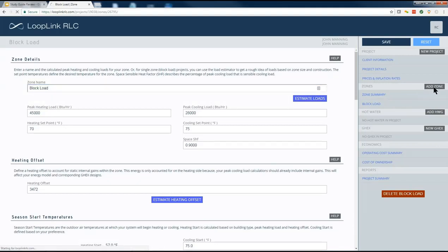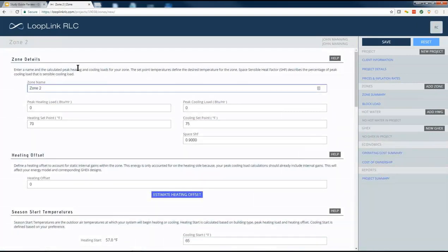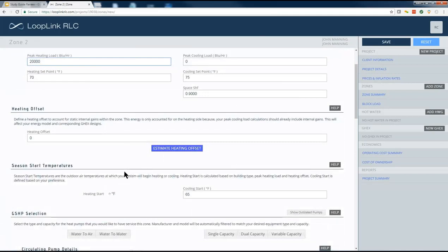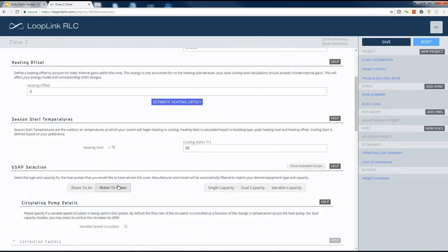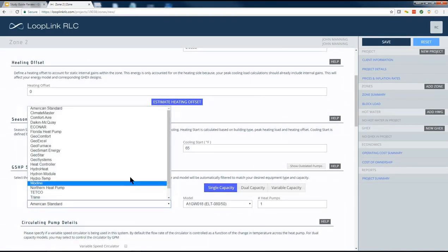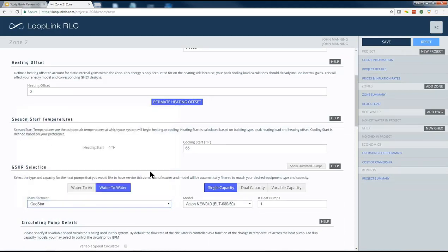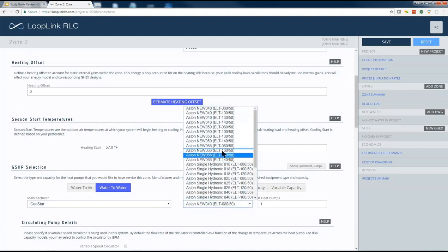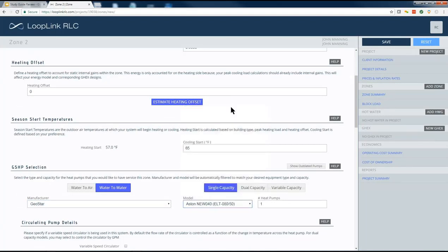So let's go ahead and make this example just a little bit more interesting. Let's say the homeowner has a forced air unit for the house, but maybe they want to get fancy and they're going to add a garage, right? And let's just say they've got 20,000 BTUs per hour of just heating load. They want to heat the floor with a radiant system. So I'm going to go ahead and put a 20,000 BTU per hour heat loss on that side. I'm going to go ahead and choose a water-to-water unit. I'm going to have to provide some guidance here. There we go. The smallest unit we've got is a 3.5-ton unit. We'll go ahead and grab that.